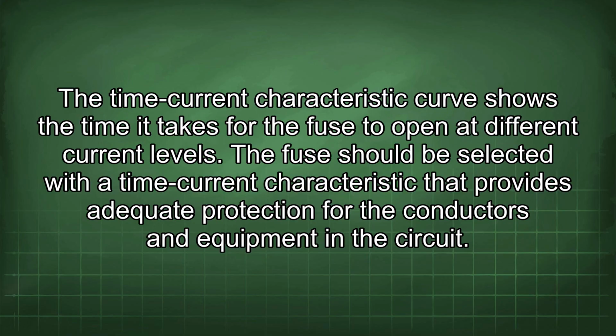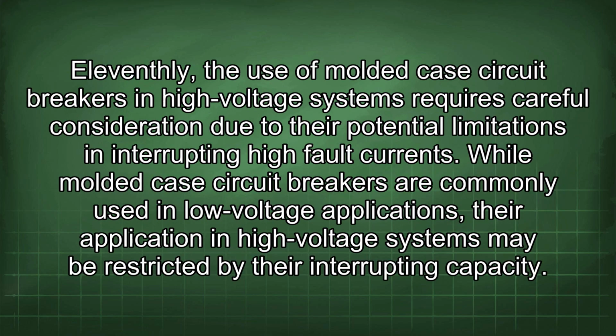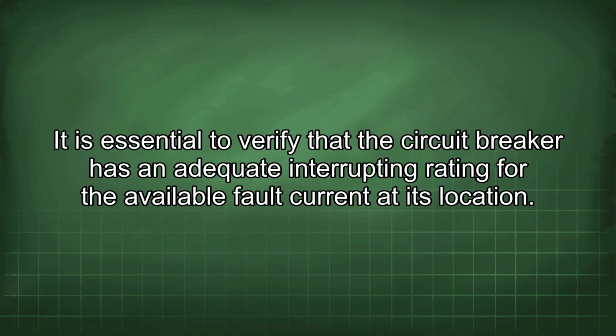Eleventhly, the use of molded case circuit breakers in high voltage systems requires careful consideration due to the potential limitations in interrupting high fault currents. While molded case circuit breakers are commonly used in low voltage applications, their application in high voltage systems may be restricted by their interrupting capacity. It is essential to verify that the circuit breaker has an adequate interrupting rating for the available fault current at its location.